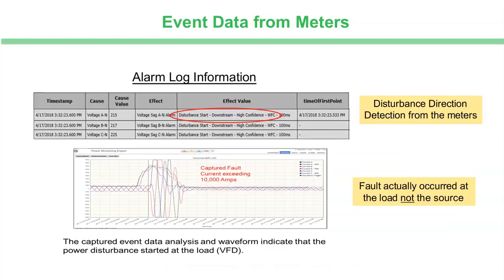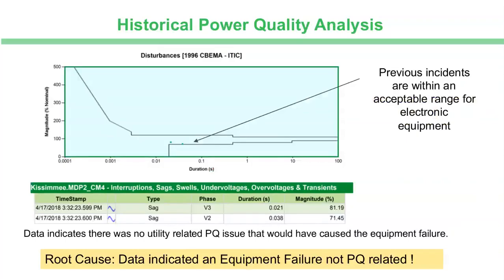And so this is the actual alarm log showing that there was a disturbance and that it was detected as being downstream by the disturbance detection in the meters. And in the waveform capture, you see the actual fault current exceeded 10,000 amps. So the manufacturer made the very good point that power quality is not a single event all the time, that you could have a lot of little events that over time degrade your equipment and lead to failure.